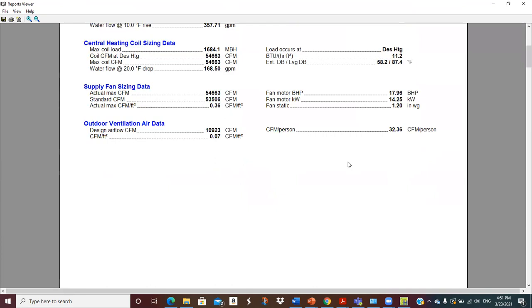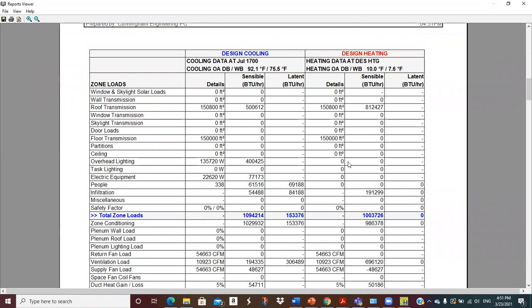Here is really where the rubber meets the road. These are the zone loads — a breakdown of components: roof, overhead lighting, electric equipment, people sensible and latent, and infiltration. Those are the loads we input in this model. This is an interior space, so typically we would have window solar loads, but because it's all interior, we don't. We add all this up and get the zone loads.